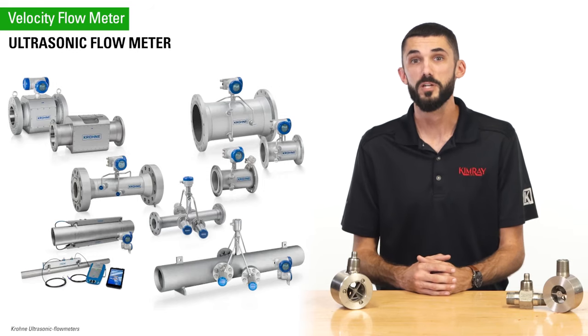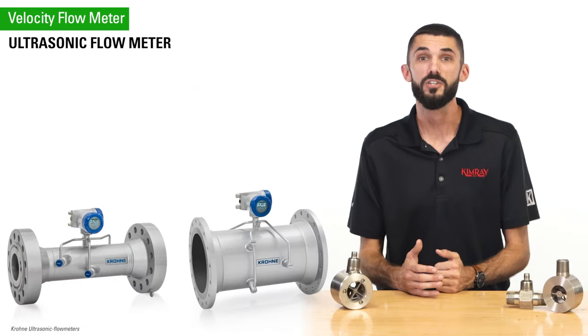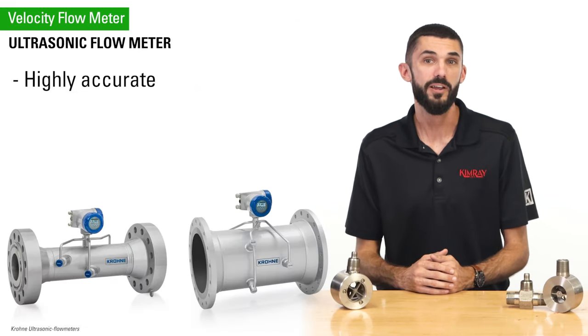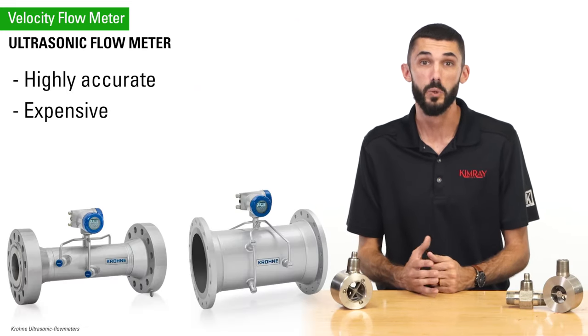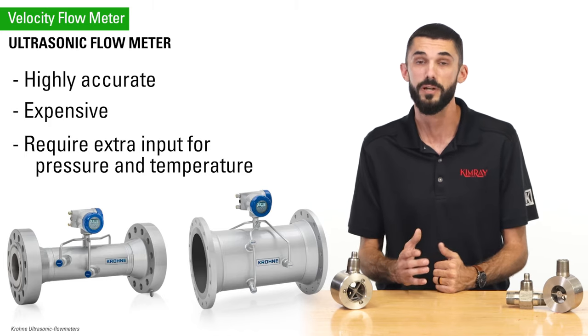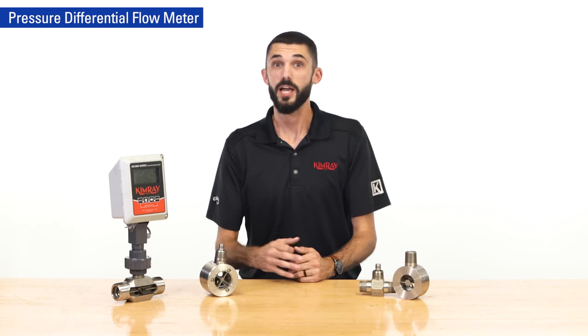Ultrasonic flow meters measure the difference in pulse transit time that travel from an upstream transducer to a downstream sensor and vice versa. Ultrasonic meters are highly accurate but very expensive and require extra input for pressure and temperature.